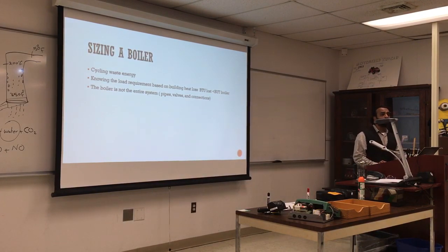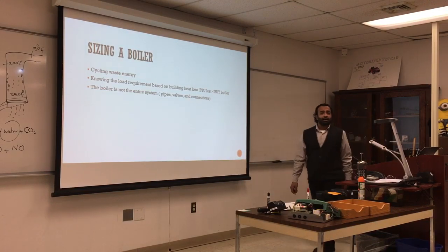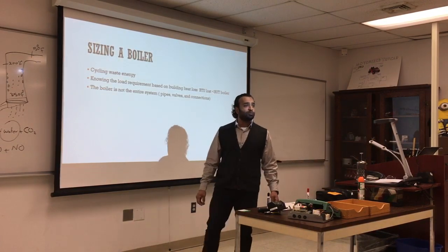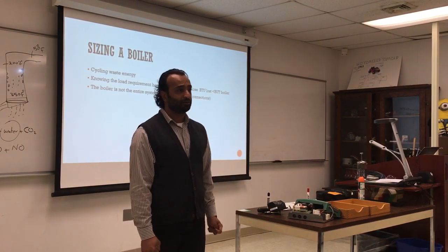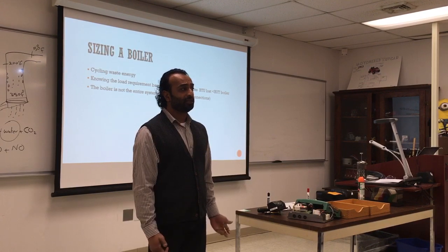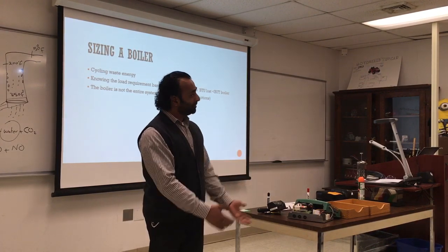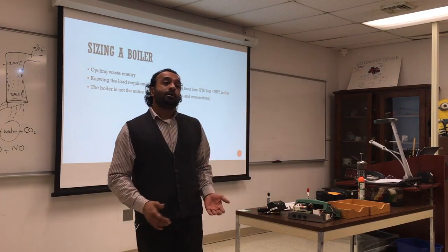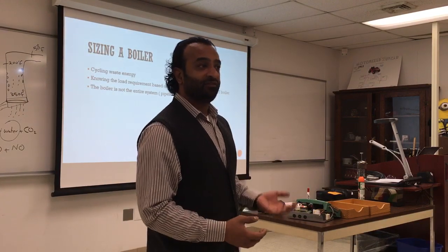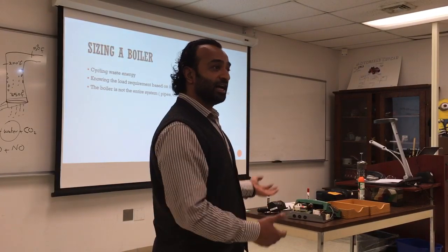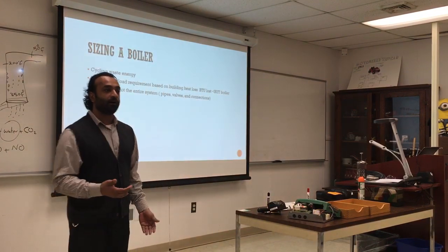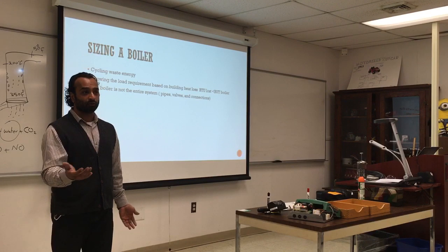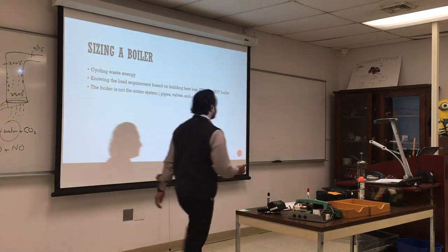Another mistake people make, especially with forced air, is they size the duct for cooling, then they add a furnace later. Is that duct going to be efficient? No. It's different BTUs for heat than the BTU for cooling. So the other way around could be better. If the furnace for forced air was designed for heat and you want to do cooling, probably you could. And the delta T is different for cooling and heating.